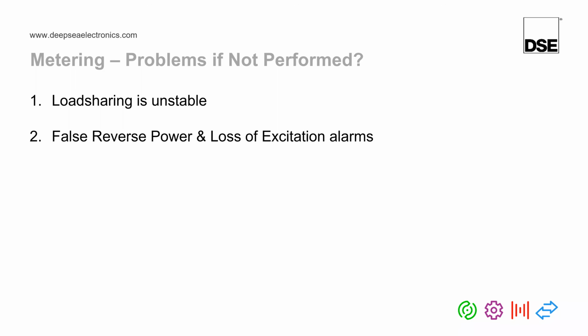I've just seen now someone's asked the question, can a 1 amp CT secondary be used with DSE controllers rather than a 5 amp CT secondary? The answer is yes. Most of our high-end controllers, really 6000 series and up, support 5 amp secondary and support 1 amp secondary CTs. There are pros and cons for using 1 amp over 5 amp and 5 amp over 1 amp, but unfortunately we do not have time to go over those during this course. But yes, with our synchronizing and load sharing controllers, it is perfectly possible to use a 1 amp CT if you wish.